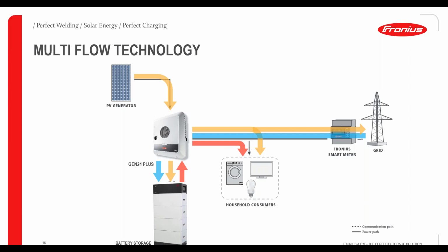You can even add and retrofit an existing system with another inverter on the AC side - you AC couple the existing system. Communication still happens between the smart meter and the hybrid inverter, because the hybrid inverter needs to know if there is surplus energy going to the grid, and it decides that surplus energy can be taken to charge the battery instead. With this additional inverter on the AC side, even if it's not a hybrid inverter, it can effectively play the role of a hybrid inverter in this installation.